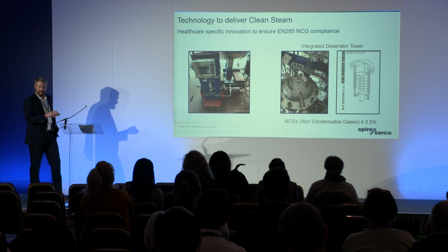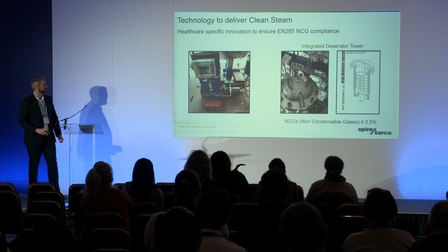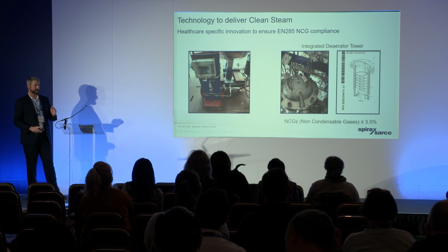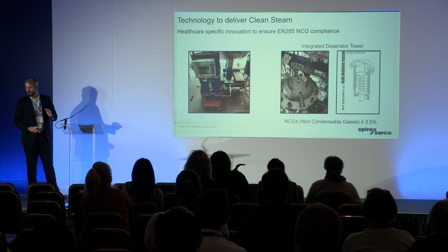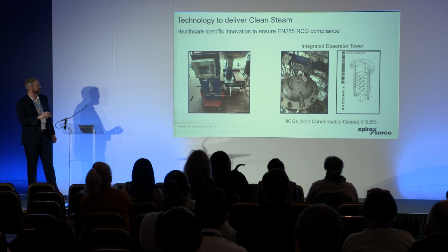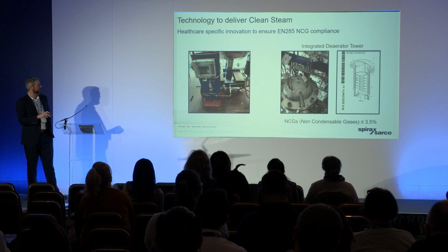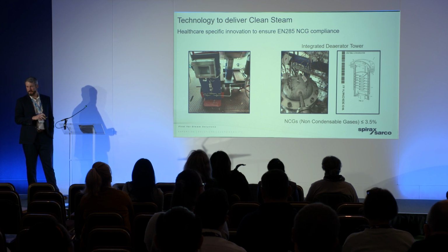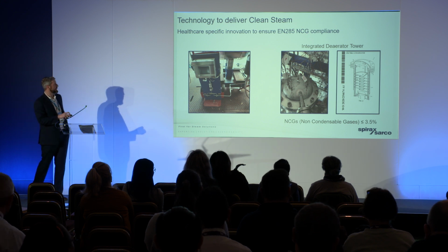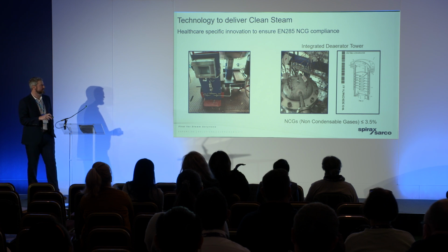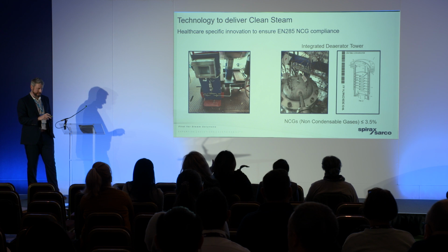This piece of equipment here is called an Orbisphere, and one of the markers for non-condensable gases is dissolved oxygen. So we were able to continuously bleed our water from our clean steam generator and cool it and measure the amount of dissolved oxygen. So we were able to prove out that we could always deliver within 3.5% non-condensable gases.